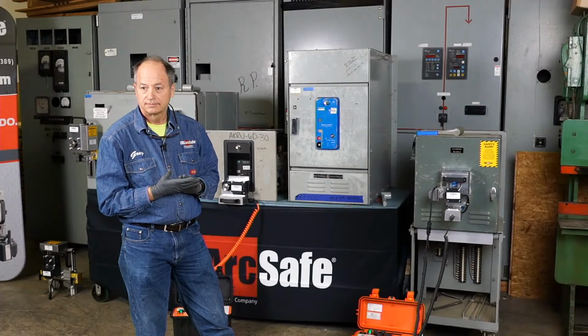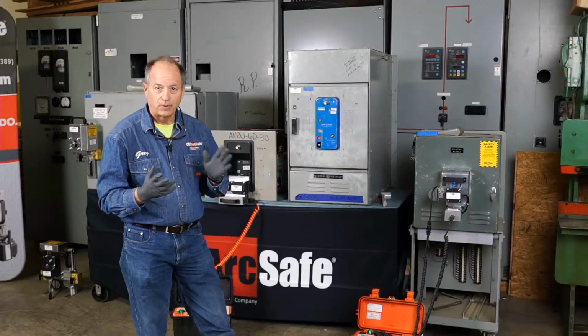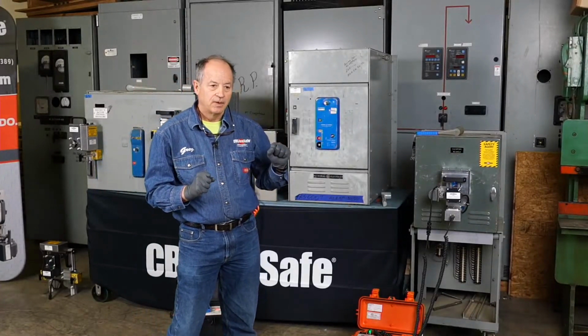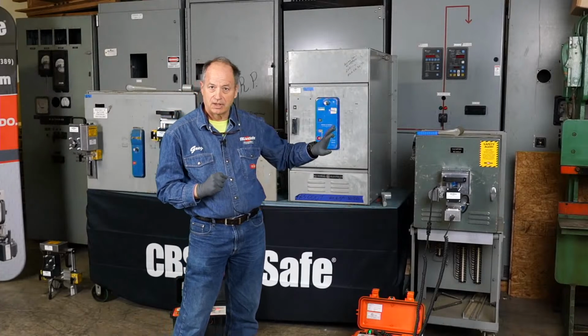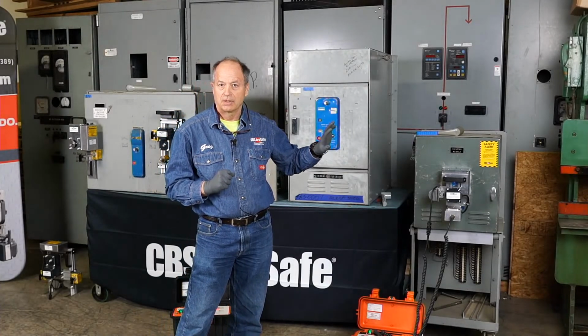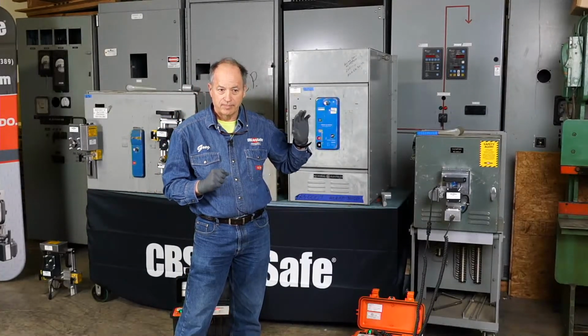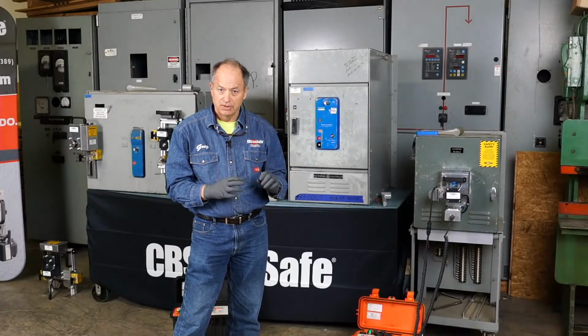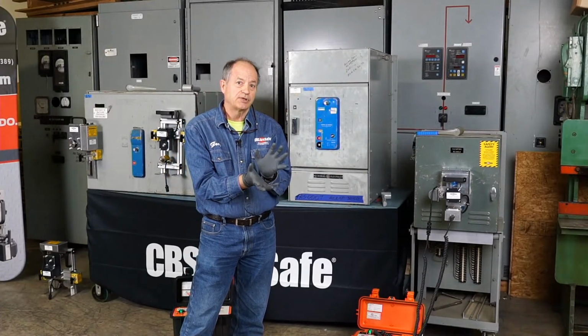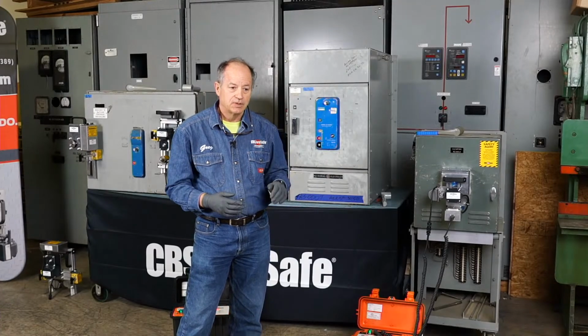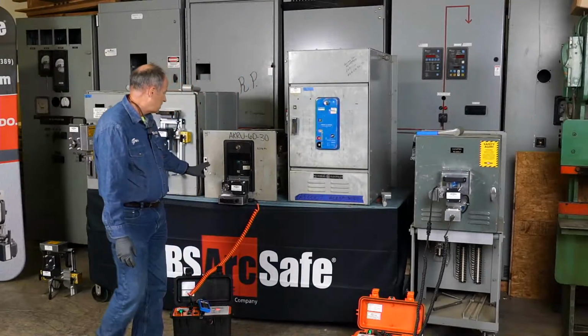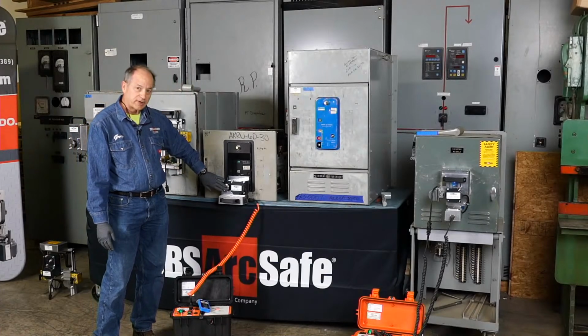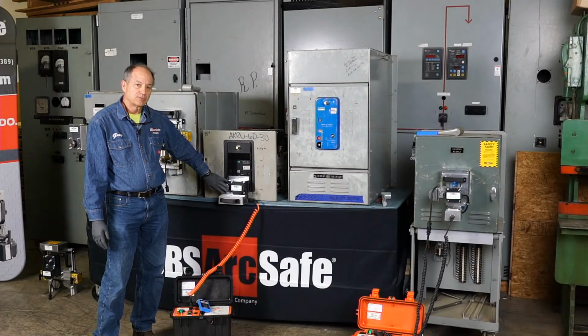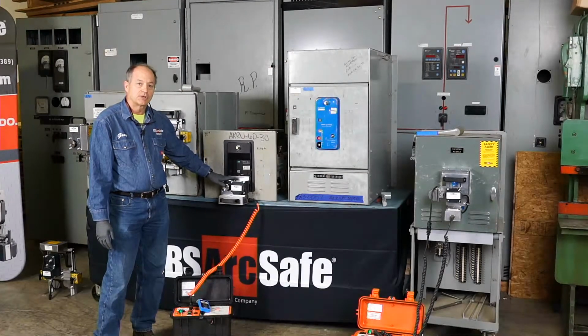So the question is, is this product just for opening and closing, or can it rack in and out as well? One of the things to understand is there is not enough space on a lot of the faces of the breakers, or based upon how a system is built, that you can just put one thing on there to do everything. So with an AKD8, I don't have space available, nor can I leave the racking mechanism door open and be able to charge, close, and trip the breaker.